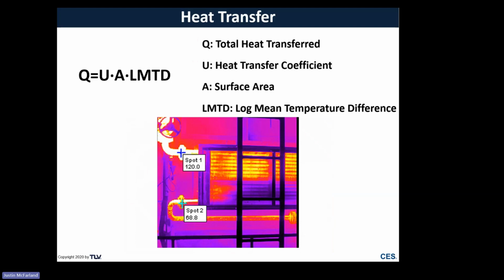And then things like flooding, so temperature stratification. If we're not able to easily drain condensate from the process heater, then we can view this as effectively removing surface area from the heat exchanger. Now, we're not actually removing surface area, but we're flooding a portion of it with water, and understanding that the amount of BTUs available in steam is much greater than BTUs available in water, as well as the heat transfer rate there, to simplify things, we like to see it as just simply removing area. And so if we change our area, then that also changes our Q value.